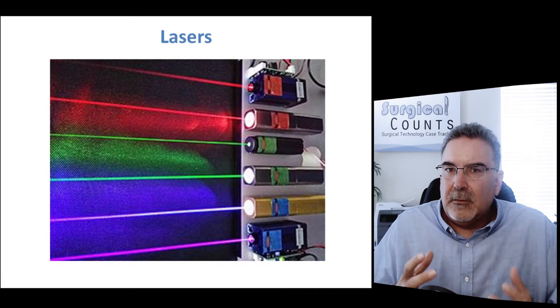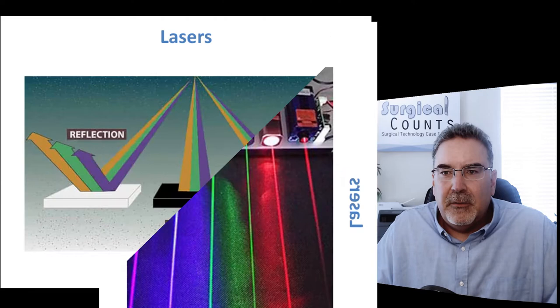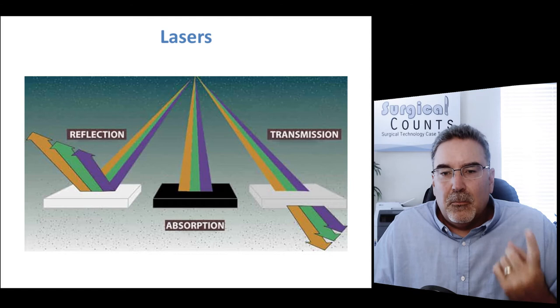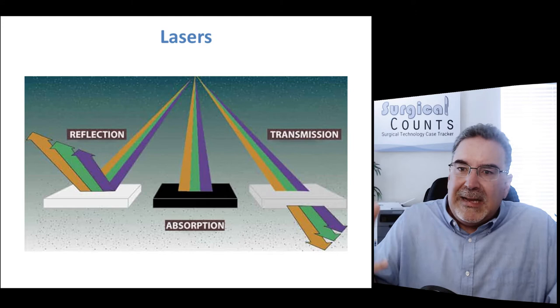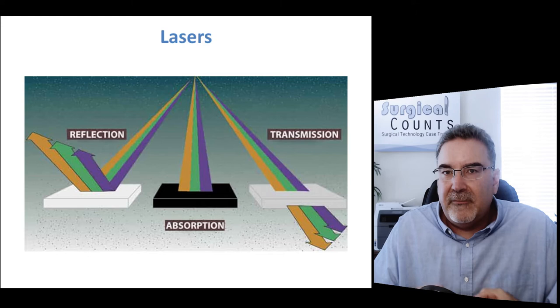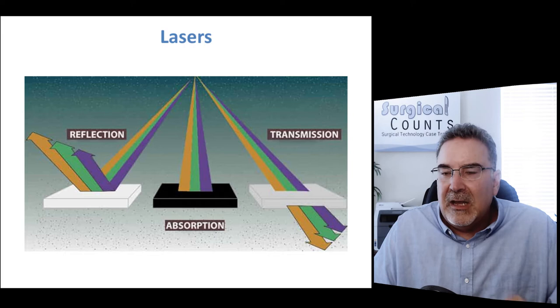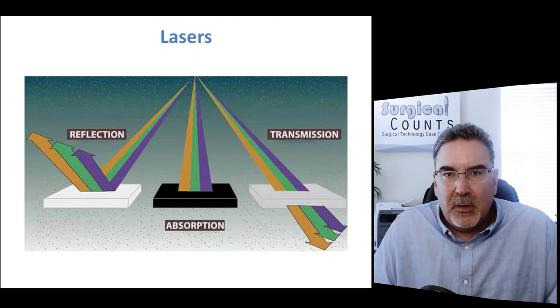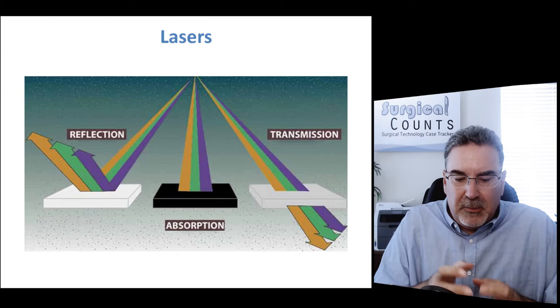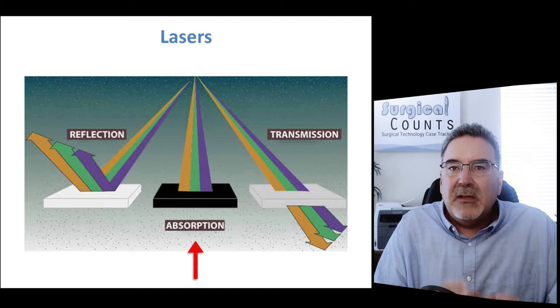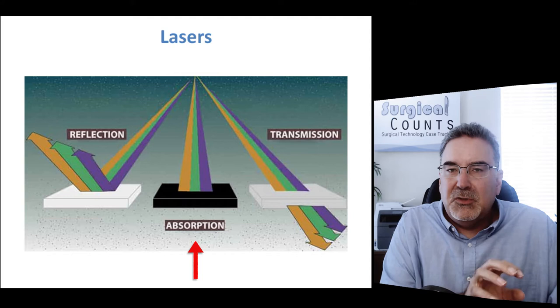Why is color so important? It has to do with the way light interacts with different materials. There are three interactions: reflection, where light bounces off the material like a mirror; absorption, where the light is sucked in and its energy stays in the material; and transmission, where light passes straight through like the material isn't even there. The interaction we care most about for surgical lasers is absorption — when a material absorbs a certain color of light, it gets very hot and either vaporizes or cauterizes.